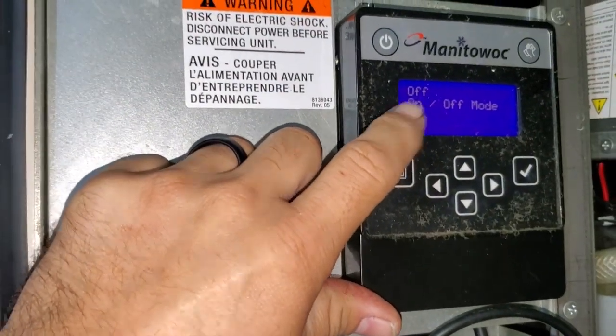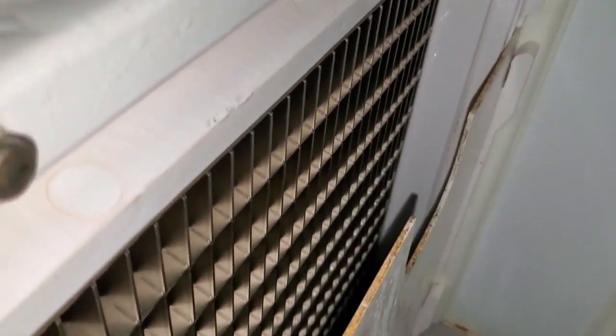Once I corrected the water flow problem, I put the unit into wash mode and let the water circulate and get rid of the rest of the ice. Now we've got all the ice off of the evaporators, and we can go ahead and start diagnosing. I have a feeling it's going to be working fine now that we got water pressure to the machine, but we're going to go ahead and go through everything.